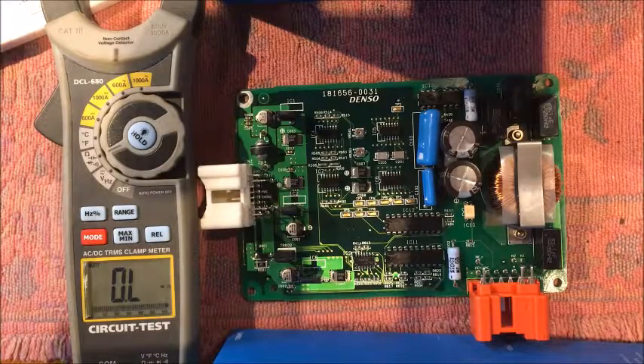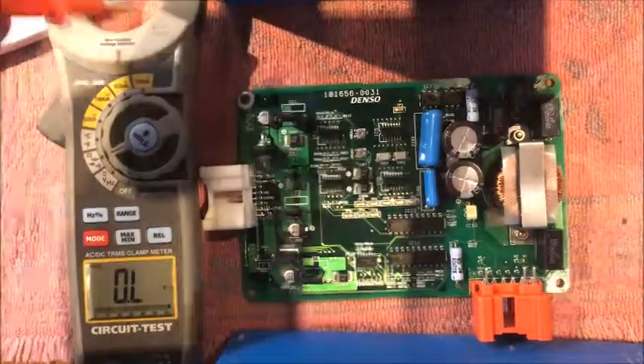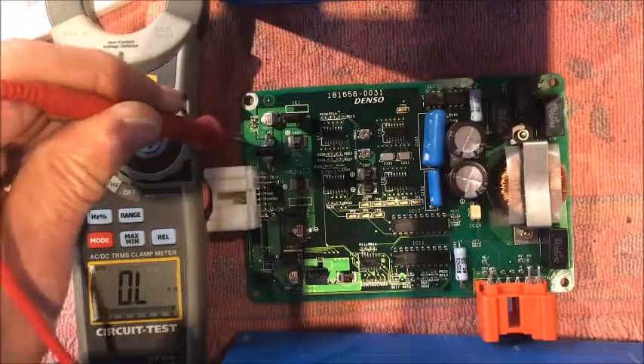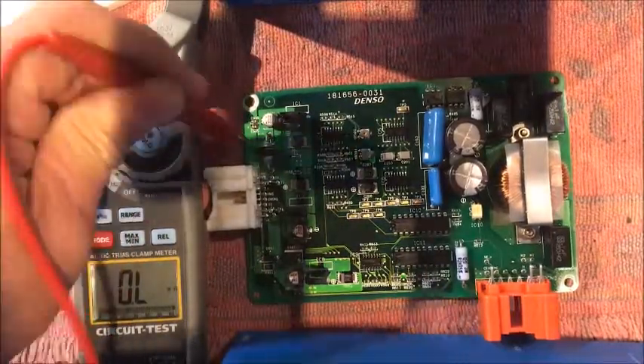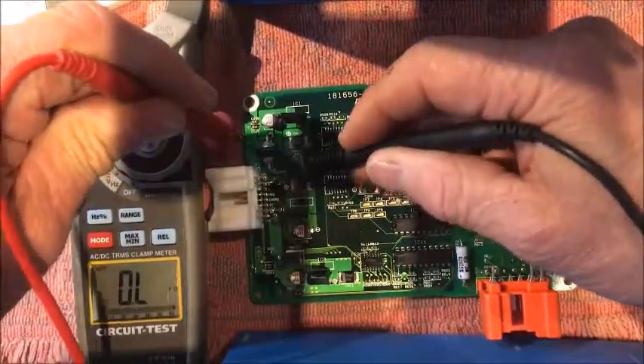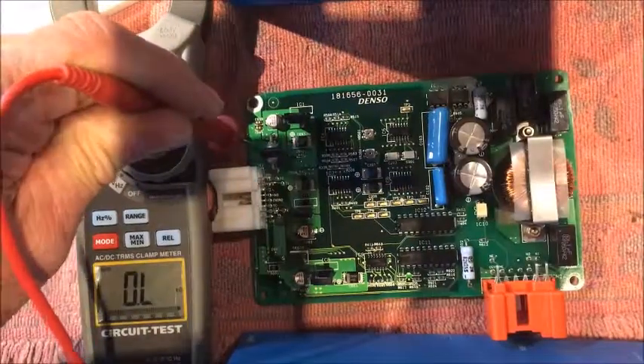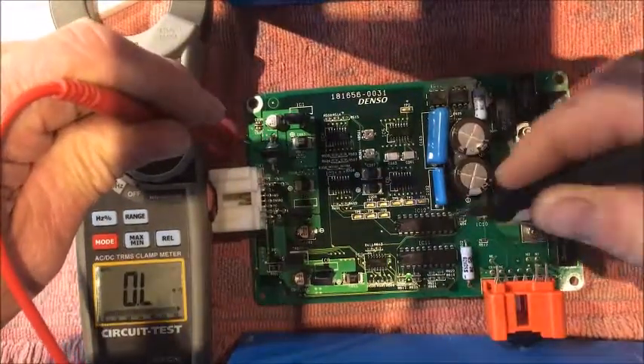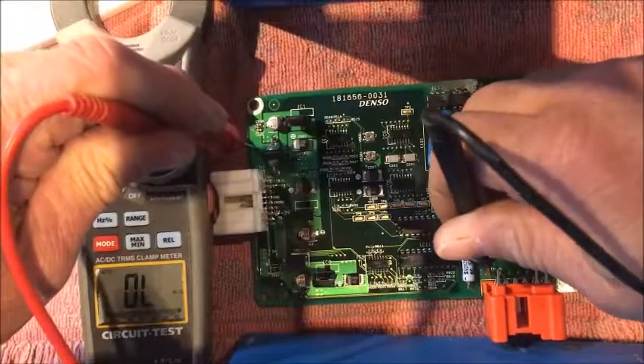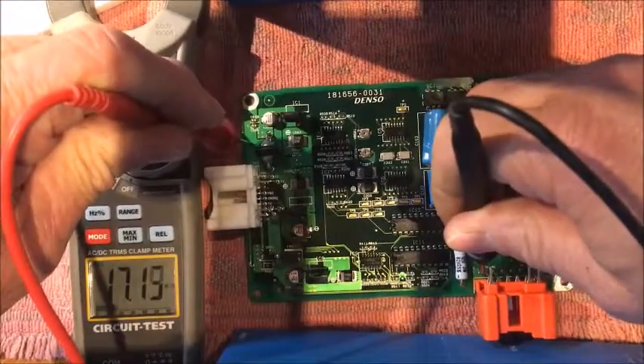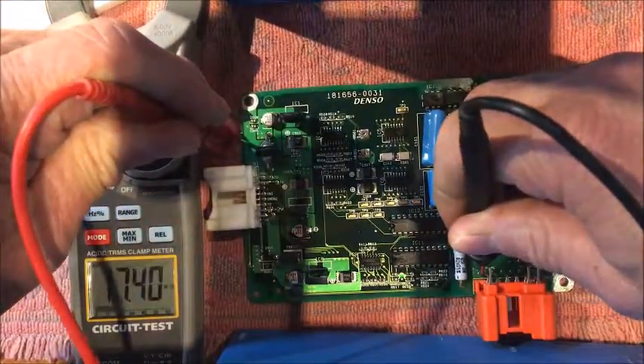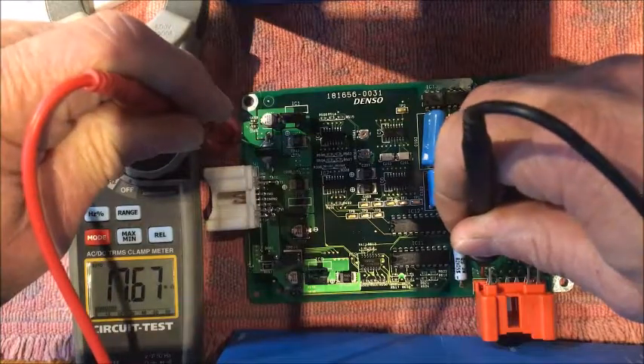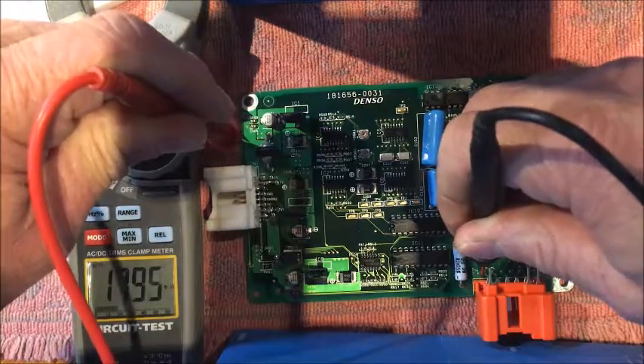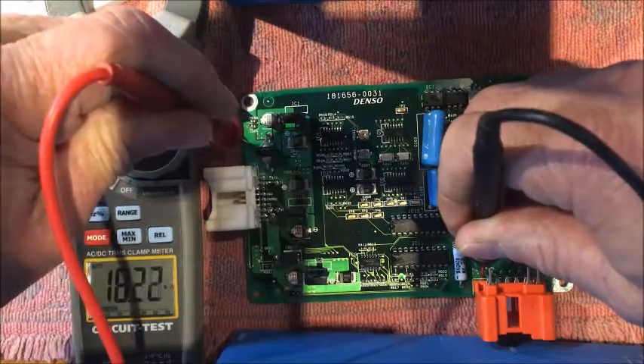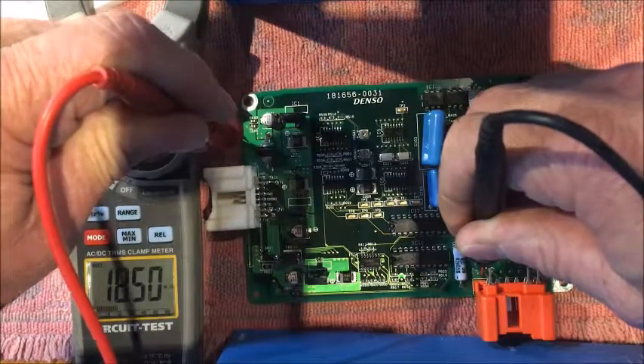Right now, just to do some active testing here, to keep this all sane: I'm going to go from the low voltage ground, which is right there, and double check that I got a zero connection there. Then this is the high voltage ground over here, and you can see that comes in at about 17 megohms with just an ordinary ohm meter, that's in one direction, with the positive lead of the meter going to the low voltage ground.